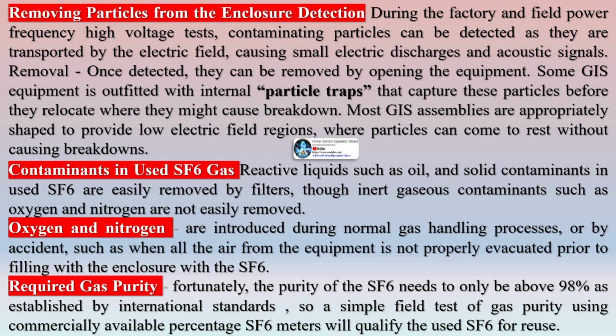During the factory and field power frequency high voltage tests, contaminating particles can be detected as they are transported by the electric field, causing small electric discharges and acoustic signals. Removal. Once detected, they can be removed by opening the equipment. Some GIS equipment is outfitted with internal traps that capture these particles before they relocate where they might cause breakdown. Most GIS assemblies are appropriately shaped to provide low electric field regions, where particles can come to rest without causing breakdowns.